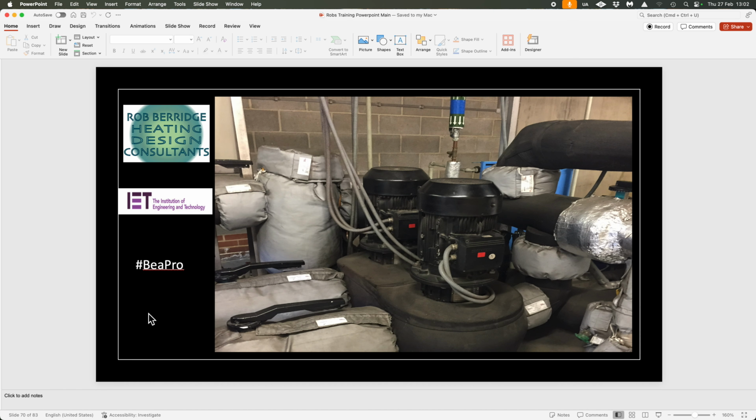Now those pumps, you can see this pipework coming in on the side here, that is DN 150. So that's quite a large size of pipework coming in and out of this unit. That there is a Spirotech dirt separator, obviously all insulated up at this point in time. Now these inverters, I could barely get my arms right the way around them to touch my hands on the other side. That was the size of them. So you're talking incredible weight. It needed big winches and stuff like that to actually get these out.